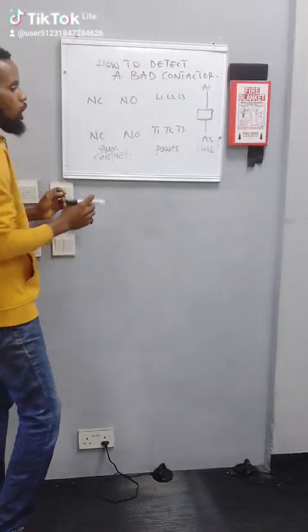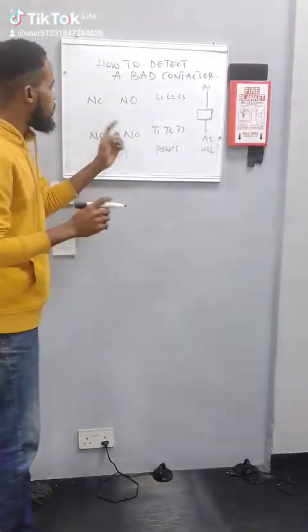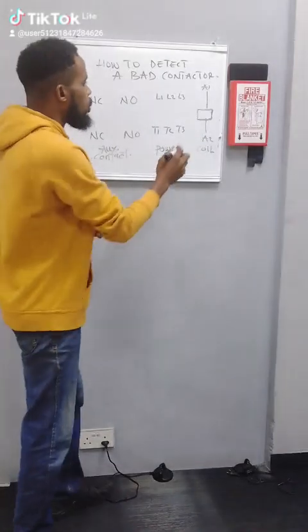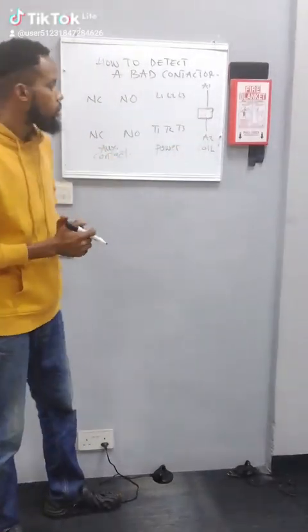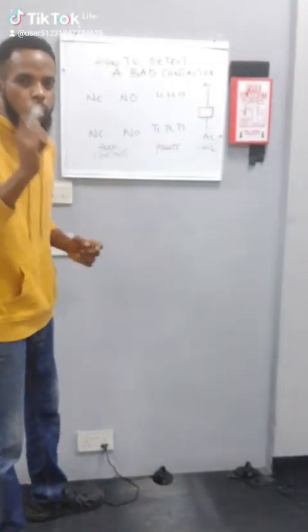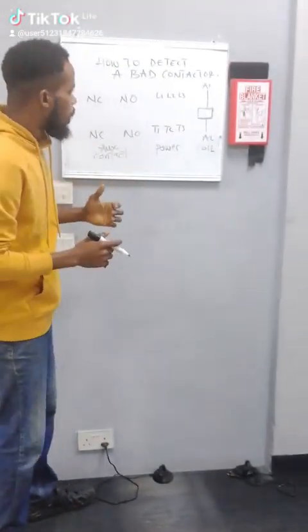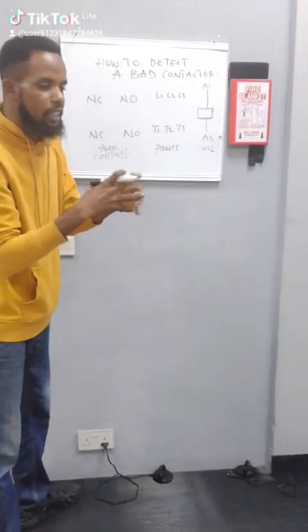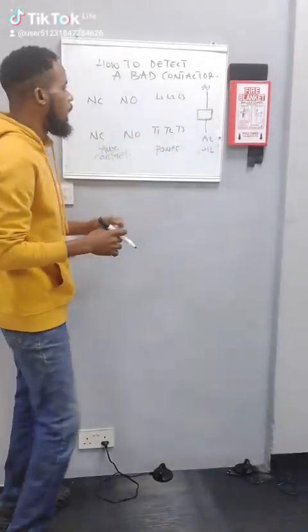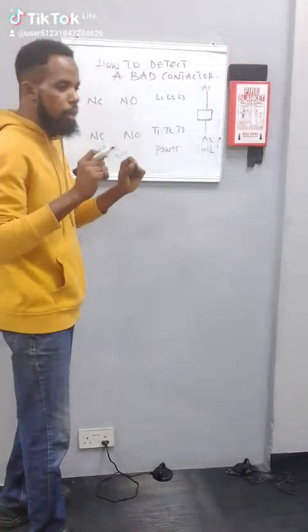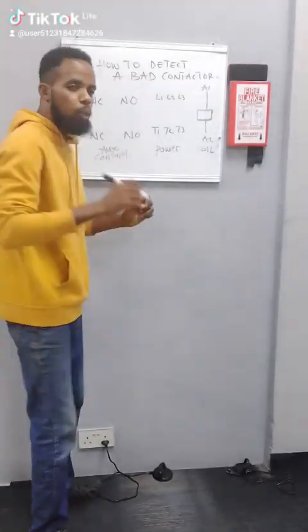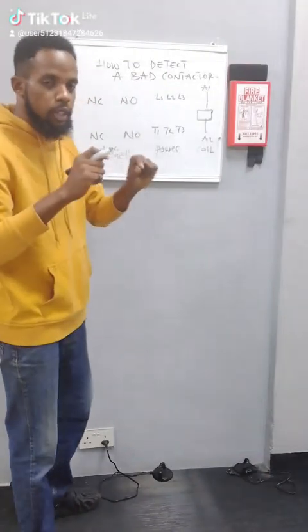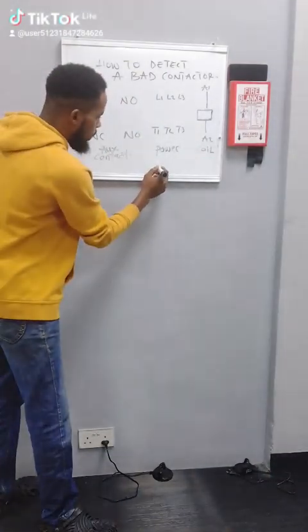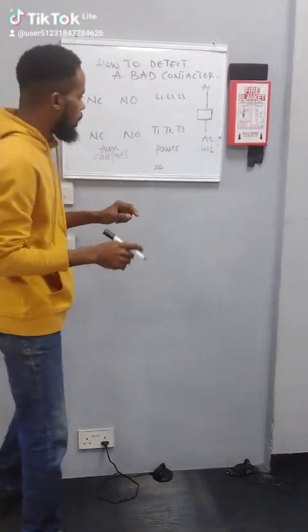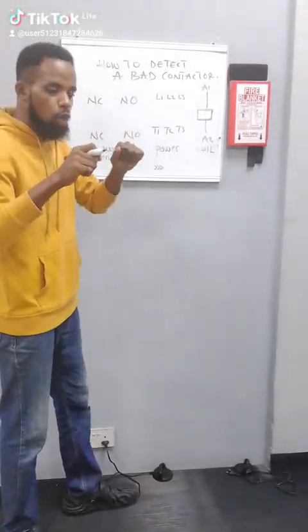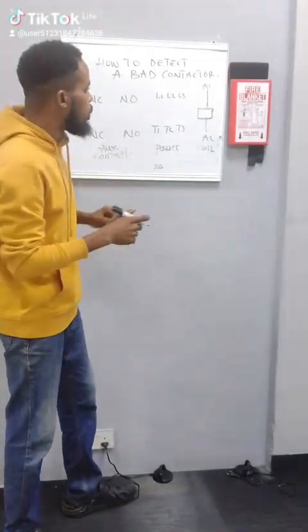contact side. So now we want to know whether the contactor is bad or not. The first thing I'm going to check is your coil. The coil can be the number one major problem of a contactor, because if the coil is not energizing, there's a problem. The first thing you do is take your multimeter and put it in the continuity setting like this on the meter.